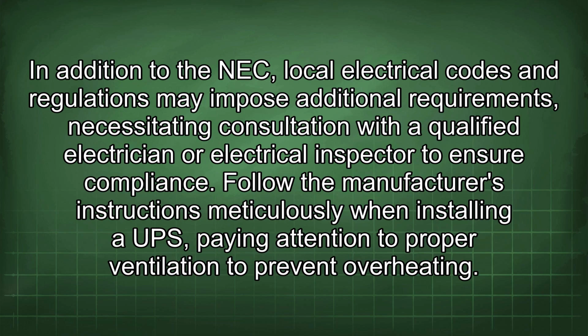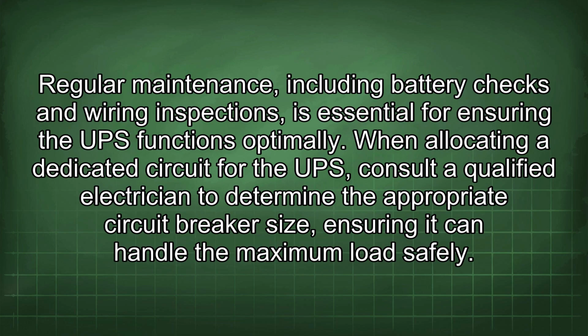In addition to the NEC, local electrical codes and regulations may impose additional requirements, necessitating consultation with a qualified electrician or electrical inspector to ensure compliance. Follow the manufacturer's instructions meticulously when installing a UPS, paying attention to proper ventilation to prevent overheating. Regular maintenance, including battery checks and wiring inspections, is essential for ensuring the UPS functions optimally. When allocating a dedicated circuit for the UPS, consult a qualified electrician to determine the appropriate circuit breaker size, ensuring it can handle the maximum load safely.